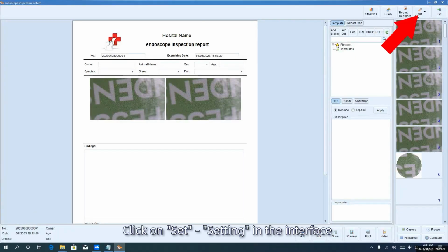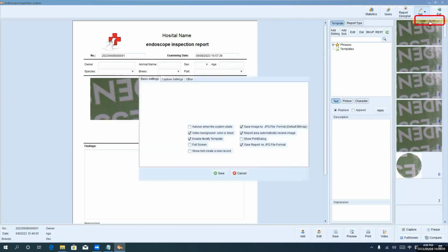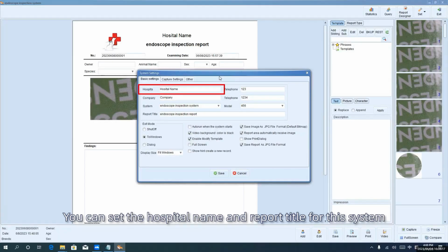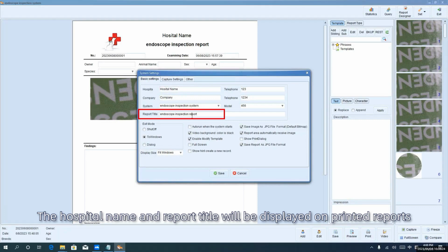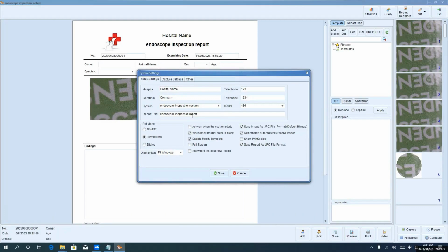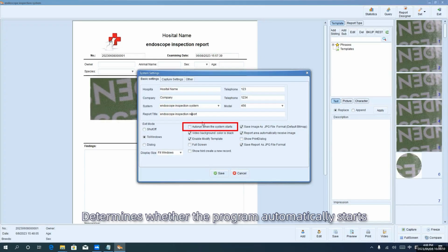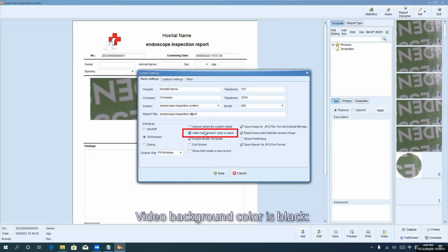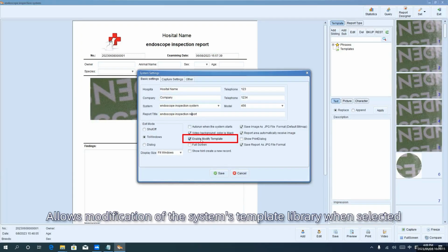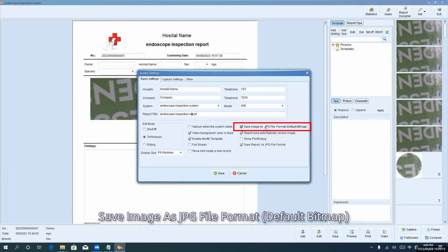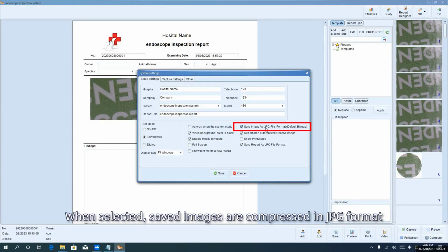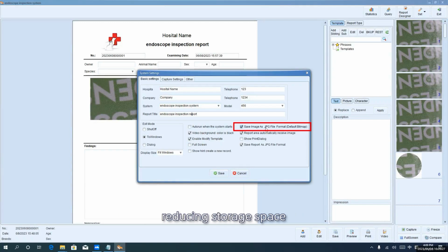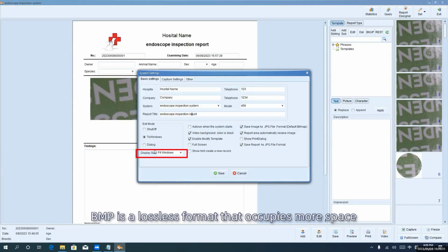System Settings. Click on Set Setting in the interface. You can set the hospital name and report title for this system. The hospital name and report title will be displayed on printed reports. Autorun when the system starts determines whether the program automatically starts when the operating system boots up. Video background color is black, sets the background color of the video area to black. Enable Modify Template allows modification of the system's template library when selected. Save image as JPG file format, default bitmap. When selected, saved images are compressed in JPG format, reducing storage space. BMP is a lossless format that occupies more space.